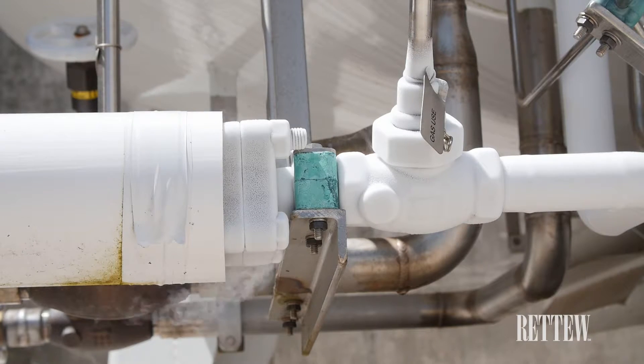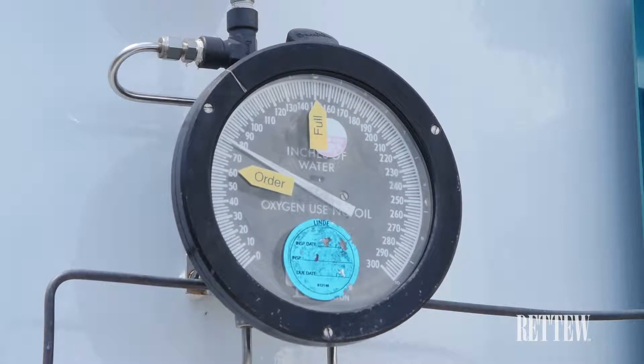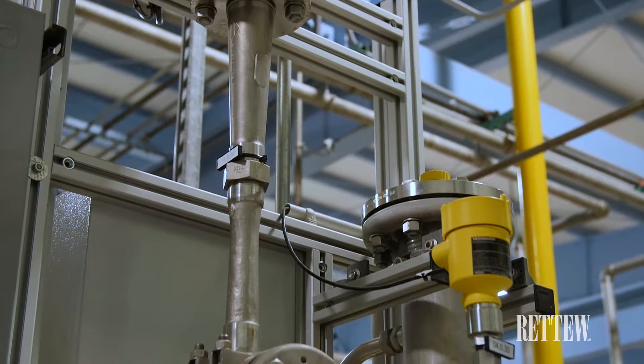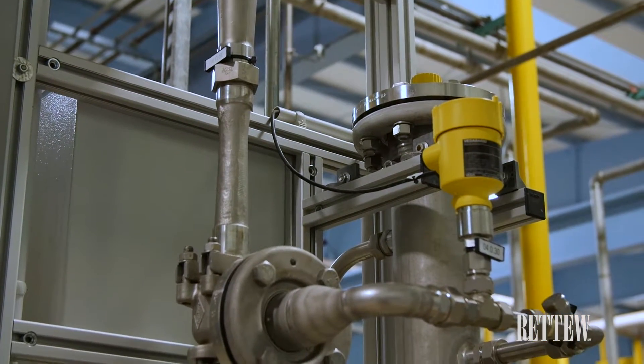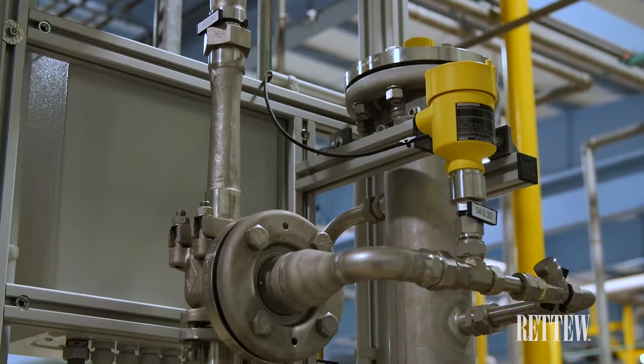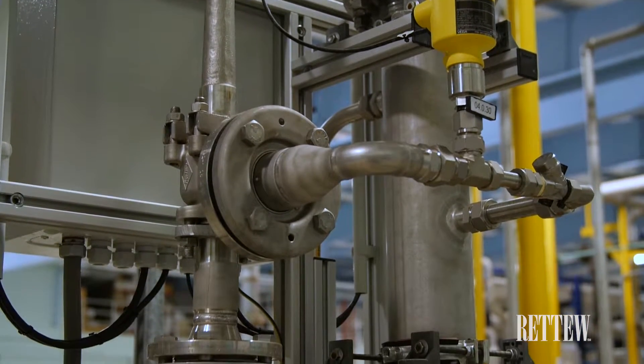Oxygen is supplied by an outside party through a liquid oxygen storage system located here at the authority. The injection system injects the gaseous oxygen into a side stream of microfiltered effluent to provide a dosing of a mixture of ozone and water for kill in our ozone contactor.